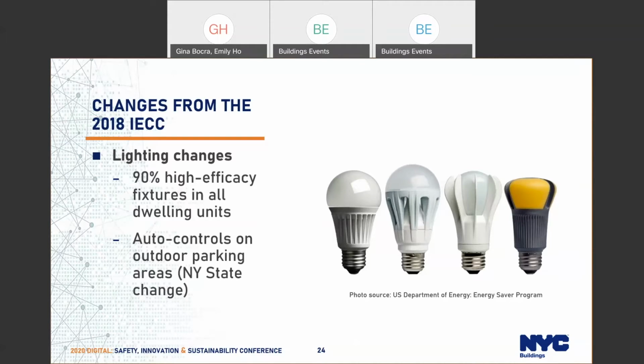Most of these changes that I've been going over originate from the National Model Code, the 2018 IECC, but New York State did make an important change on outdoor parking area lighting controls. They took language from 90.1 and added it to the ECC compliance path. What these controls require is essentially an occupancy sensor on certain lighting fixtures in open outdoor parking areas. So not parking garages, but outdoor parking areas. If you're designing a space with outdoor parking, that's an important provision to remember.